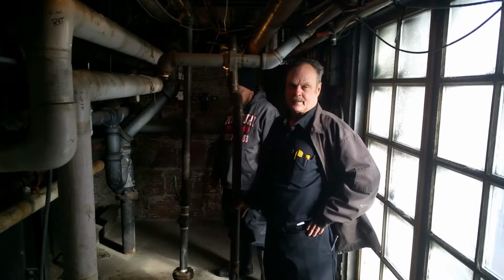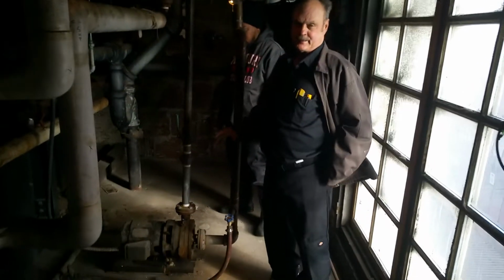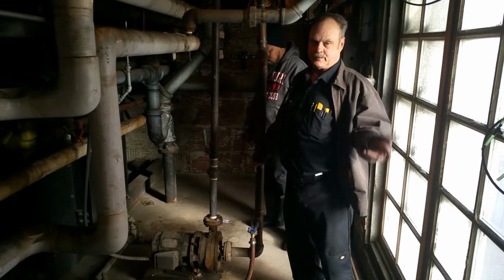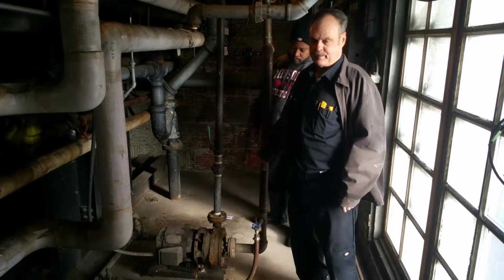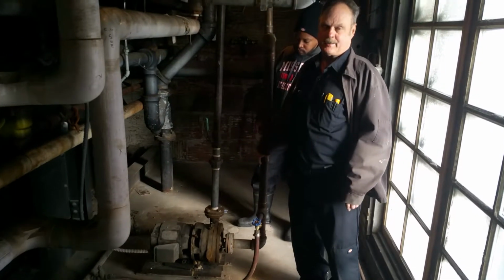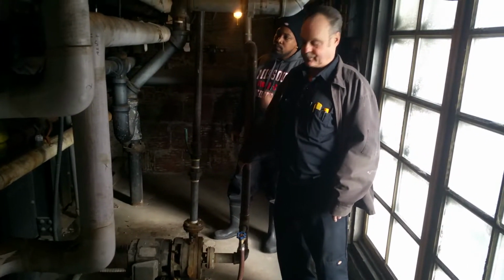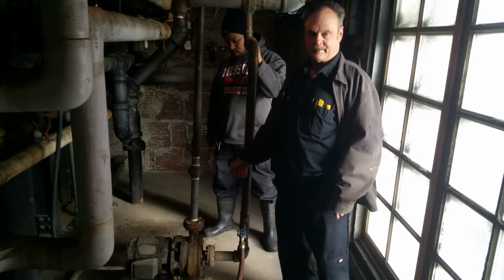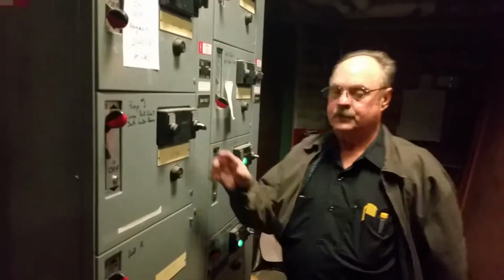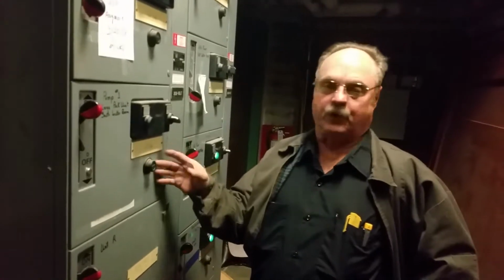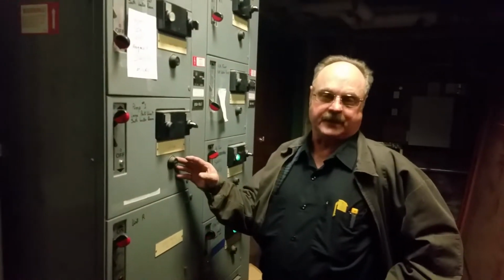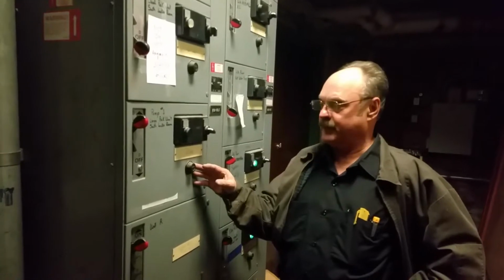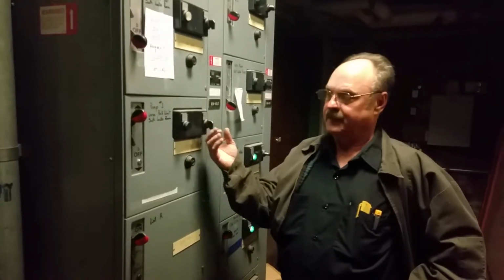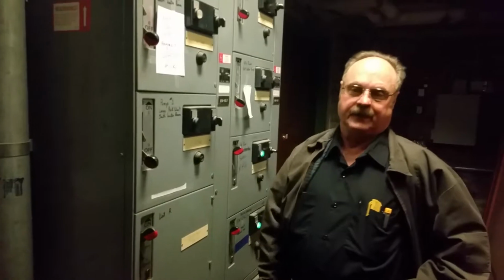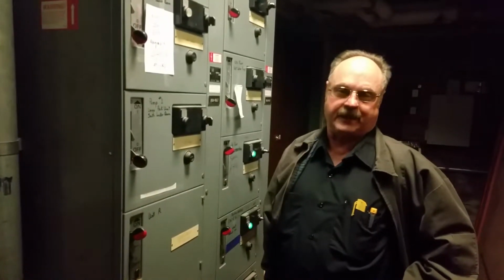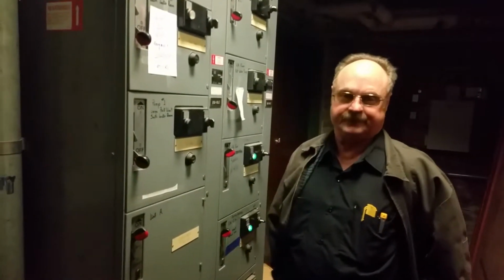And that's what we do to disconnect the compressor so it does not energize with no cool water going through the compressor. What we're doing here today, we're shutting down the south locker room air conditioning unit we just turned off in the locker room. We have to shut off the pump that feeds from the cooling tower up there to that water-cooled compressor. So this is the pump that we're going to be shutting down. Where's the disconnect? Got it back. So we're back over here by the main electrical control panel for that south locker room cooling tower pump. So we're going to shut it off, throw the disconnect, and that's the bulk of shutting down the south locker room air conditioning package unit.